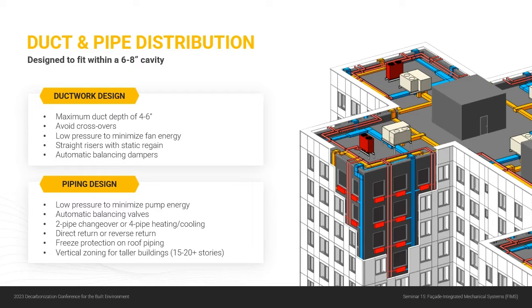We definitely want to design it as a low pressure system because we want to minimize fan energy. And the good thing is, even if it's a rather tall building, when you have a straight run of duct running down the facade without any elbows or fittings, you can actually do it with a very low pressure drop, even when it's a long duct run. And then, of course, we want to be able to balance this at every floor, so using automatic balancing dampers at each branch is probably a good idea. Now, with the piping design, similar considerations. You want it to be low pressure.